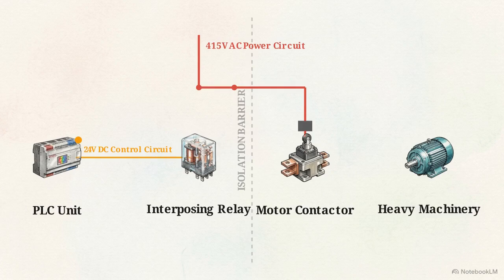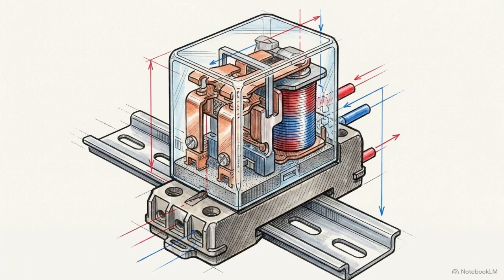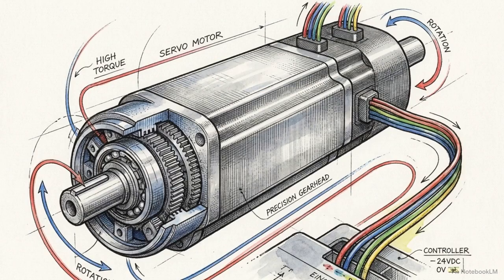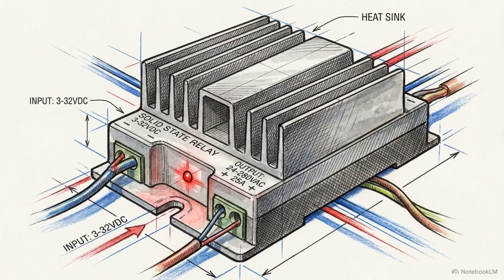That newly closed relay contact allows 415 volts of alternating current to flow out and fire a massive three-phase motor contactor, which finally drives the heavy machinery. The type of load dictates the hardware. We use these mechanical relays for slow, heavy AC loads. But for precise servo motors that require thousands of pulses per second, we bypass mechanical parts entirely and use solid-state transistor outputs that switch in microseconds.